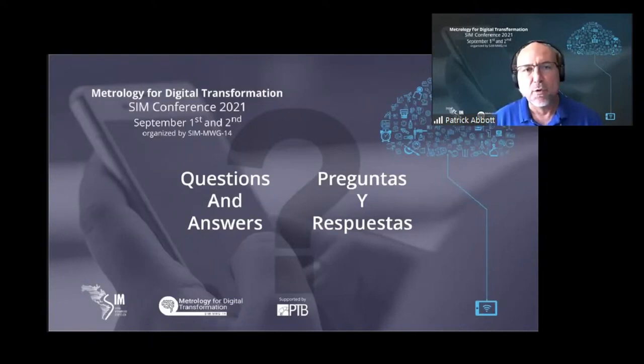Uncertainty contributions, that's a great question. Being a metrologist, you're always concerned with such things. And two things come to mind with the robots. First of all, temperature uncertainty. I don't know if you were able to appreciate the enclosed volume that each one of the robotic comparators is inside, but it's a fairly large, maybe a cubic meter or so of volume that each comparator has inside of it, plexiglass basically. And as you begin to run the automated robotic comparator, things get warm. And we've noticed that over the course of the first 3 or 4 hours we can notice a fairly repeatable pattern in terms of temperature increase on the order of maybe 0.2 to 0.3 degrees centigrade.